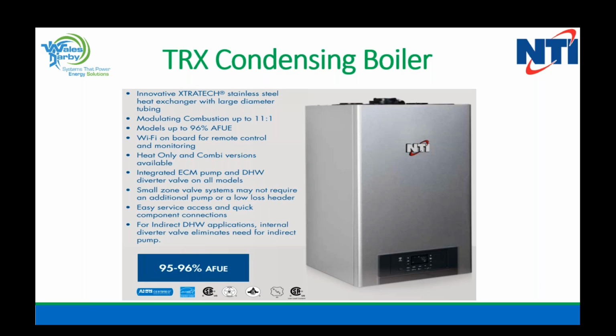You can see that it says 11-to-1 turn down. So what does that mean? This means this boiler can slide down from its high output down to an extremely low output. I know the 85,000 can go from 85,000 down to a low BTU output of 9,400 BTUs. So that's a big deal, because in all of our hydronic trainings, we're always talking about doing the heat loss, making sure you're matching the appliance to the load.